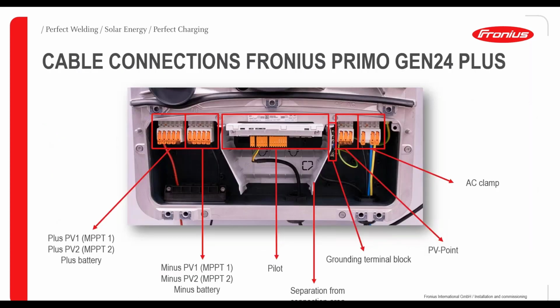So here we can see now the open inverter without the black cover in front of it. The cable connections here are now from a Fronius Primo GEN24. Maybe we go from the left to the right. We can see here the plus connections from the first MPP tracker, second MPP tracker, and the battery connection. And right next to it, the minus connections, of course, MPP and battery. The first thing we maybe see here, these are not screw terminals. So here we talk about spring clamps. You just have to open it with one click with the finger. You insert the cable and you can close it again. It's a very fast method to do and undo this cabling.